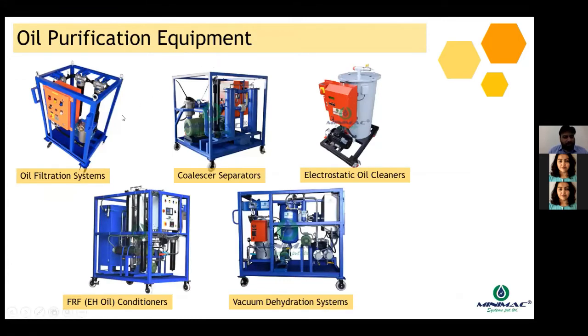Some of the oil purification equipment, so there are 5 different technologies which are offered: simple mechanical filters, coalescer based separators which can free up the free water content from your lubricating oil, electrostatic oil cleaners which are very popular for removing submicronic particles, and also sludge and varnish. The FRF or EH oil conditioners, which are commonly used for phosphate esters in power plants. So these can help you to reduce the total acid number, moisture contamination, and of course, you can also maintain ISO 4406 and NAS 1638 using the FRF conditioners. And the last one is vacuum dehydration systems, which are used for removal of all three forms of moisture from your fluids.